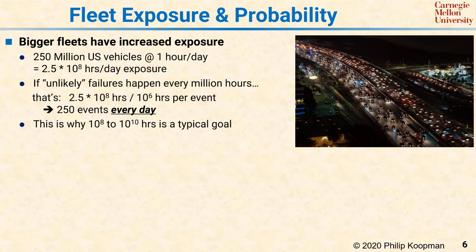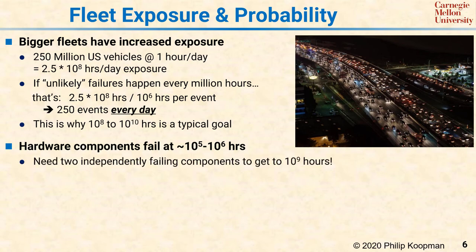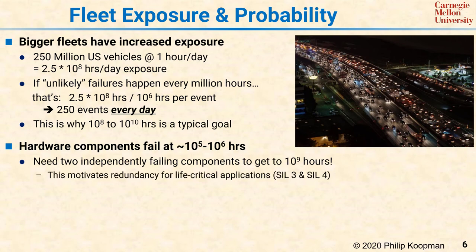Individual hardware components tend to fail every 100,000 to one million hours — comparable to non-fatal permissible failure rates, but much more frequent than is permissible for life-critical failures. The only way to deal with this reality is to use independent components so that the failure of an individual component does not make the system unsafe. This means any life-critical application — generally SIL 3 or 4 — must have redundant components that fail independently and bring the system to a safe state regardless of what single component fails.